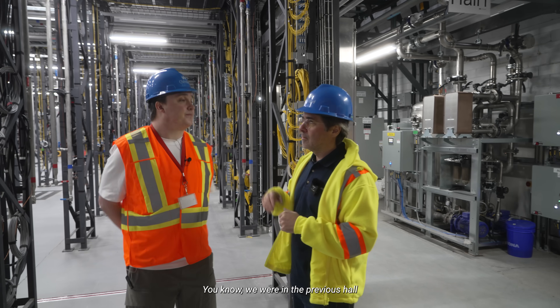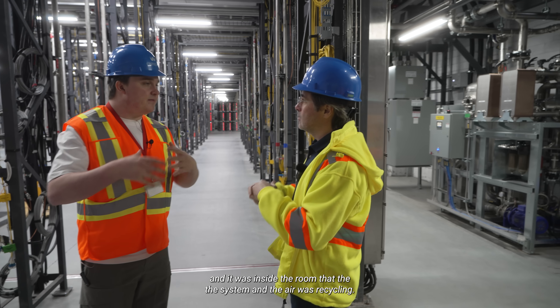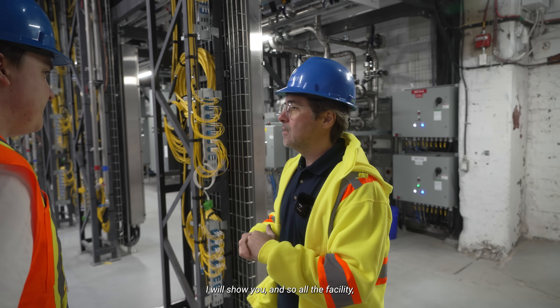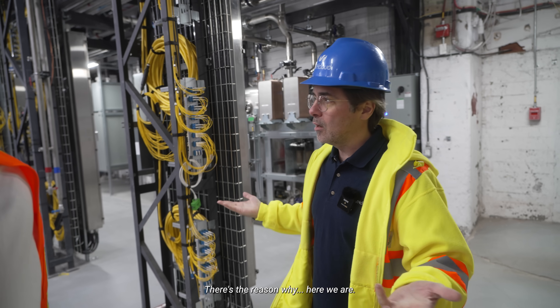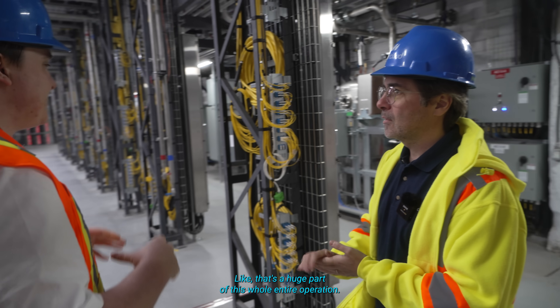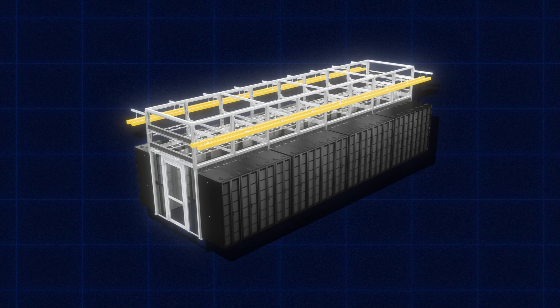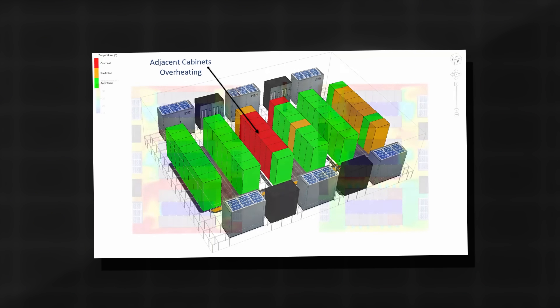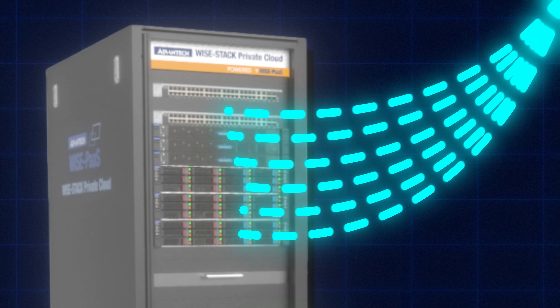Because of the design of the facility, air is recycled through the entire facility rather than just within small rooms. The architecture of servers being in rows is actually by design — an aisle containment method creates a physical barrier between hot and cold air to prevent mixing. It's noticeably warmer in between the servers and the complete opposite immediately after. There are a lot of ways to cool servers through standard fan or liquid cooling practices.